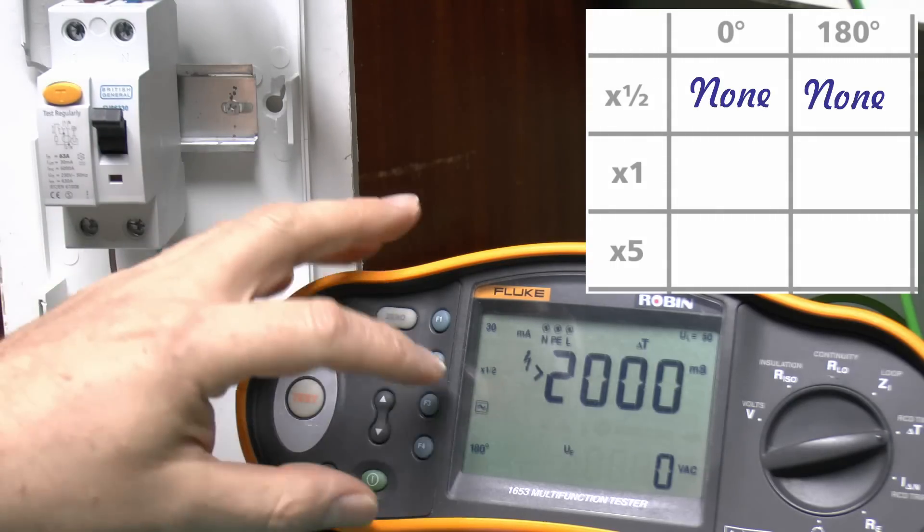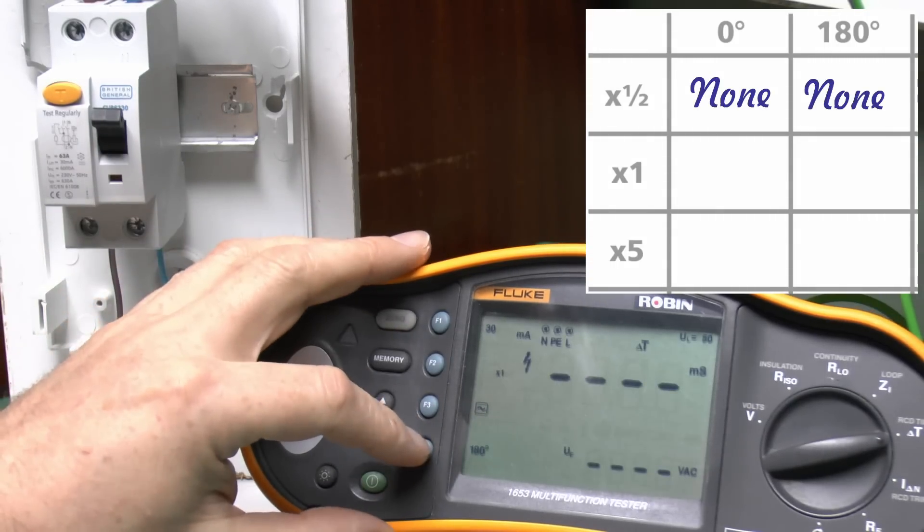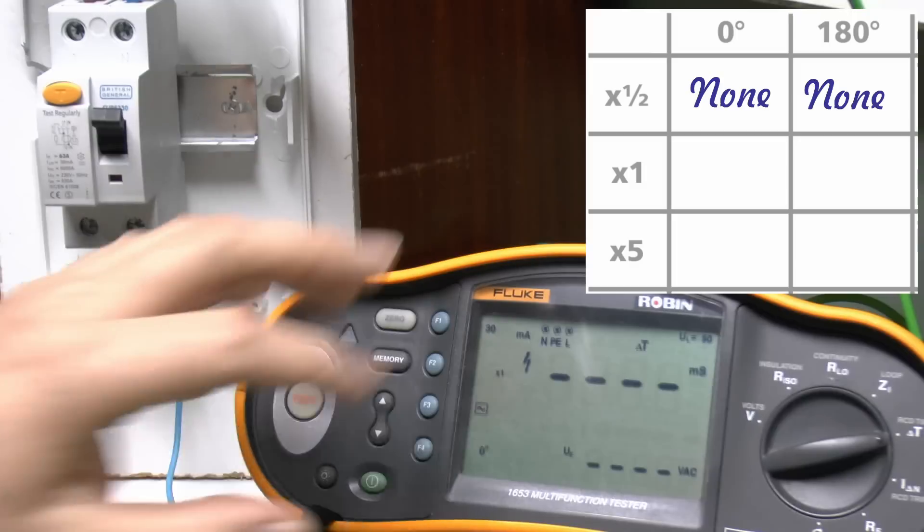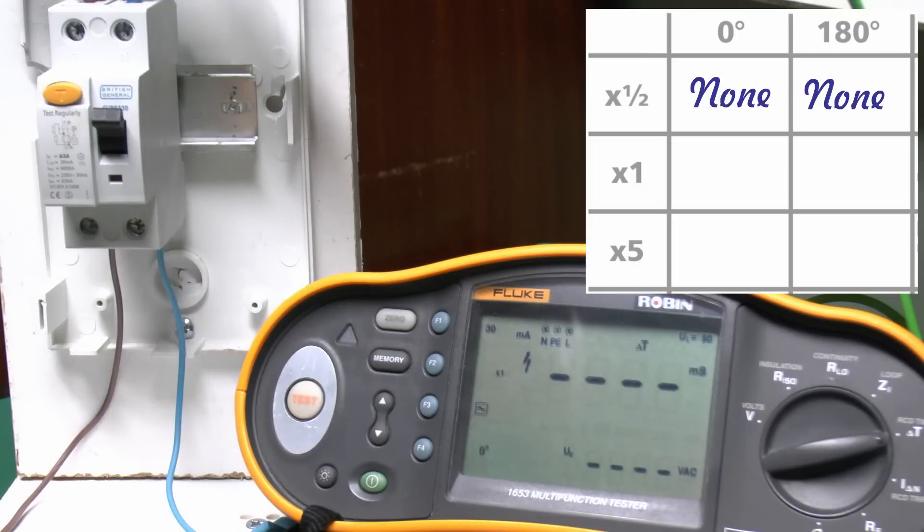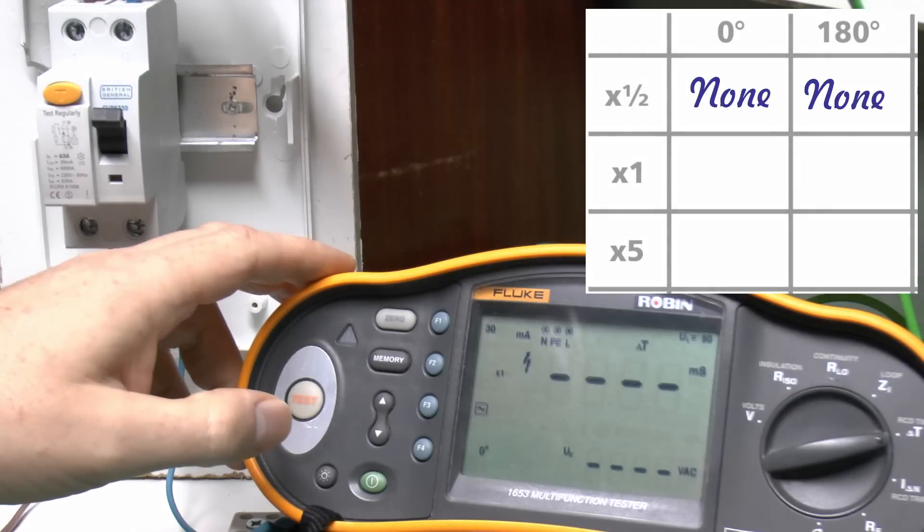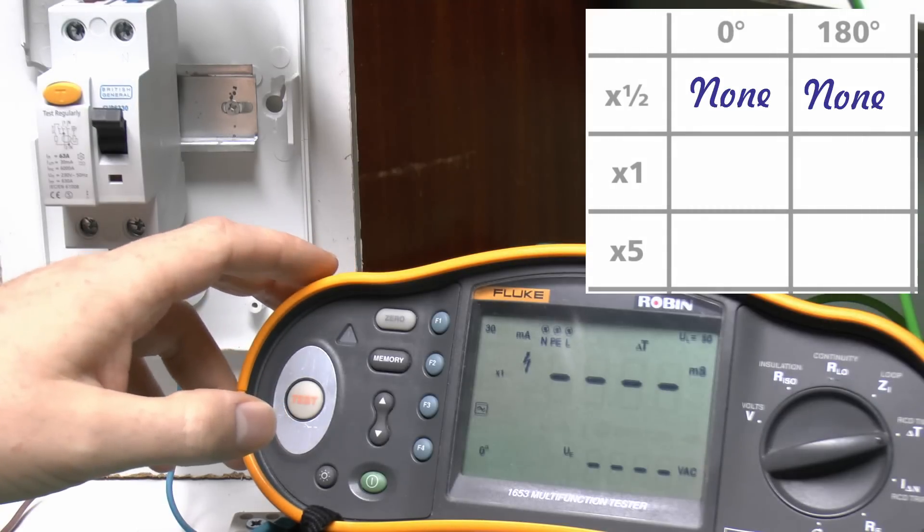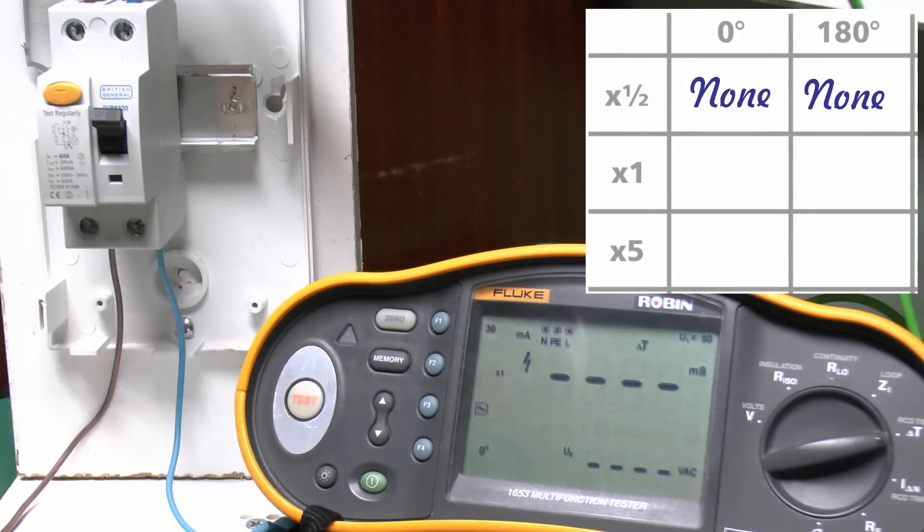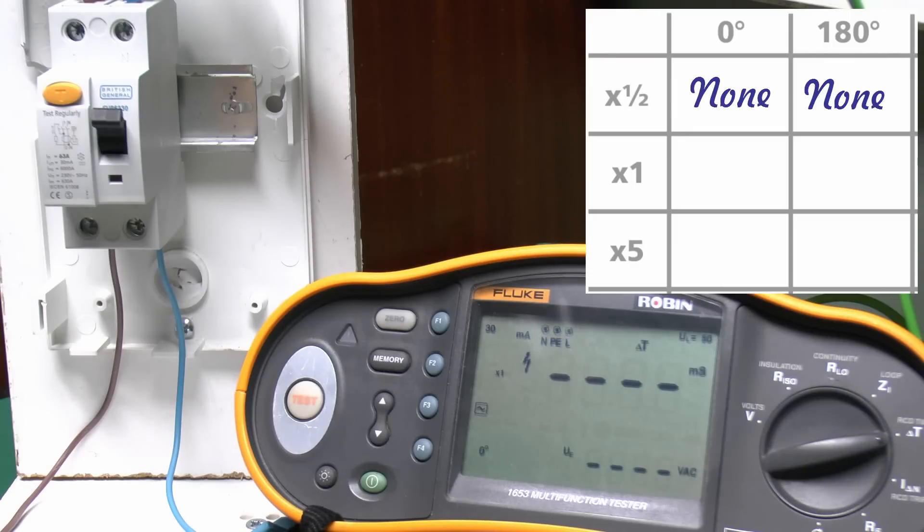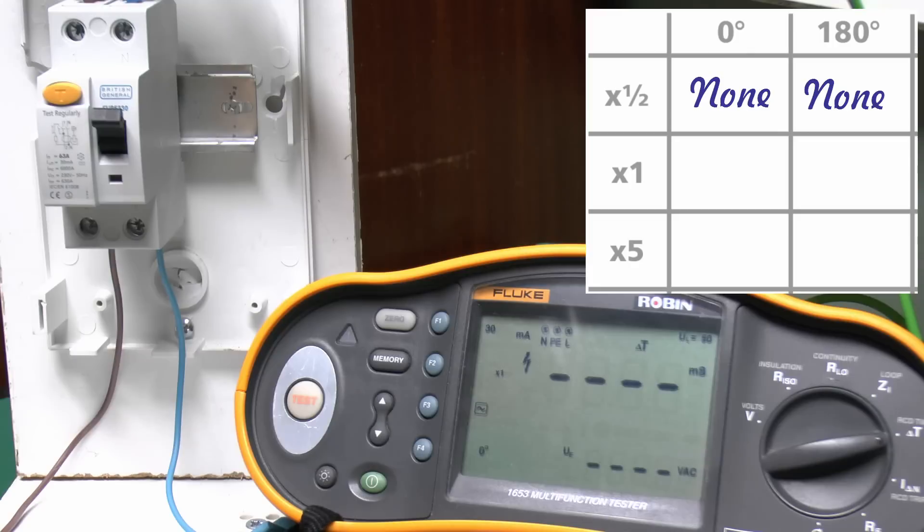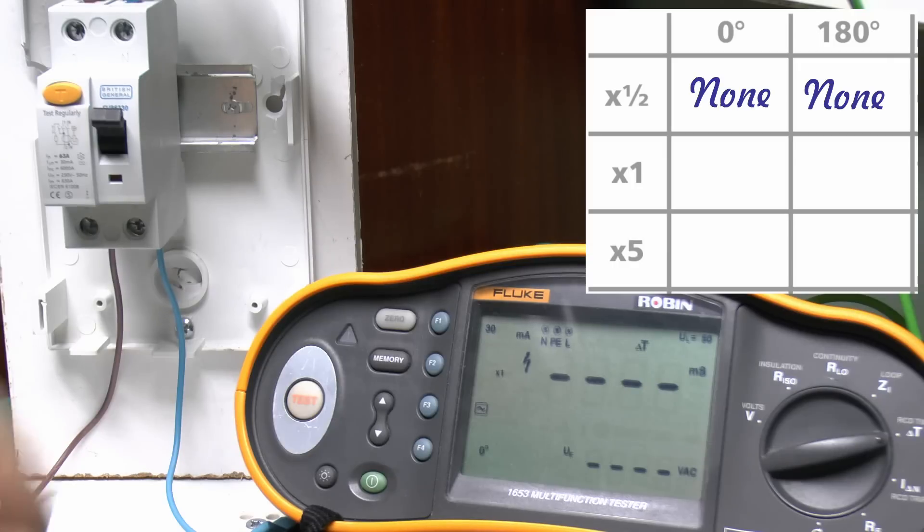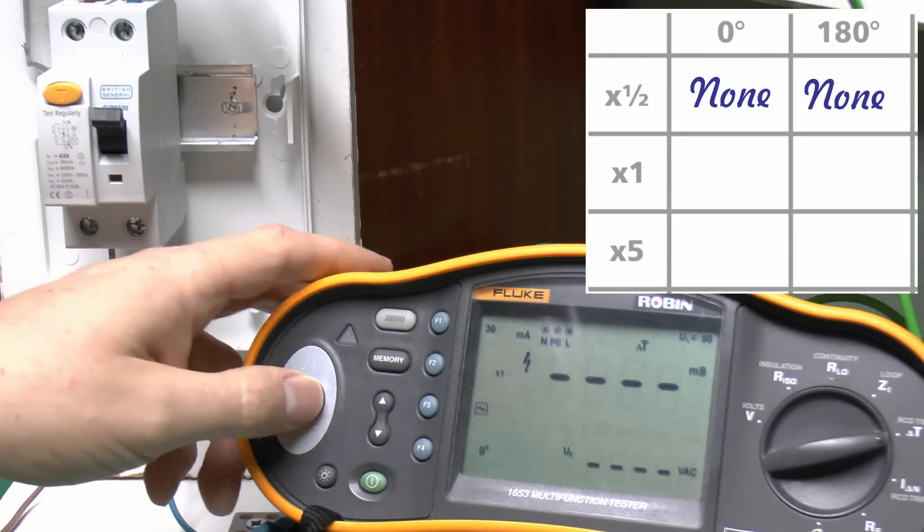So now we'll move on to the 1 setting, which will apply the 30mA test current, and this should trip, and the tripping time should be less than either 300 or 200 milliseconds, depending on which standard the RCD is made to. The more recent one is actually 300 milliseconds. Older ones made to the older BS standard would be 200, but in any case, you don't want to have figures in the hundreds. They should be considerably lower than that, and let's see what this one is.